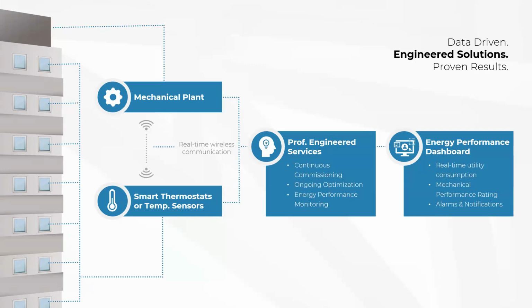But we tie that real-time wireless communication into what the mechanical plant is doing and look at it through an engineered lens, right? We are engineers here at NERVA. We then translate that into an energy performance dashboard, so that not only does the client have real-time and historical insight into their building's operation, but it also flags when the building falls out of the predicted band of operation, which is typically adjusted based on the current outdoor air temperature. That lets us understand whether the building has seen a spike in consumption outside the expected band, or perhaps a drop in consumption outside the expected band, because as soon as you're outside that band, you want to know what's happening.